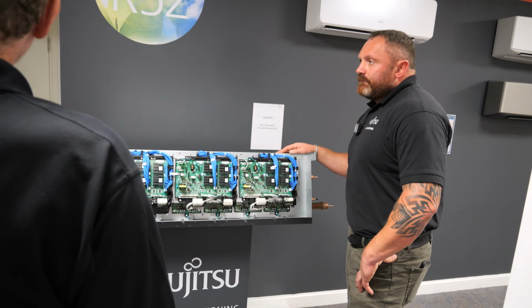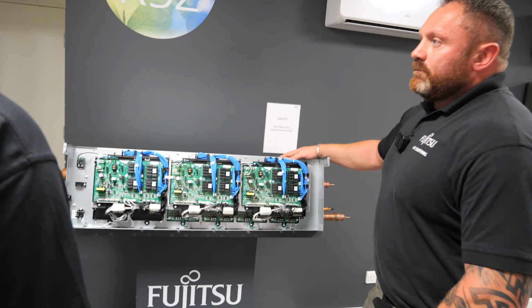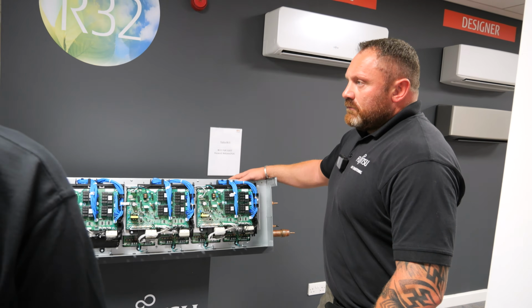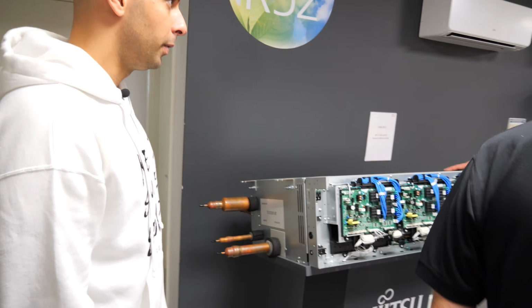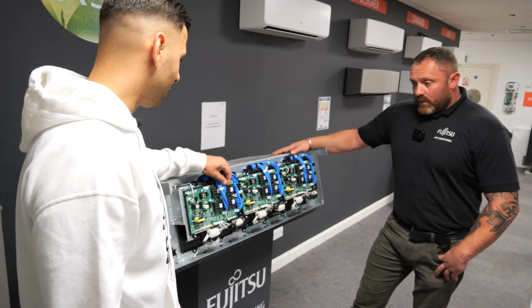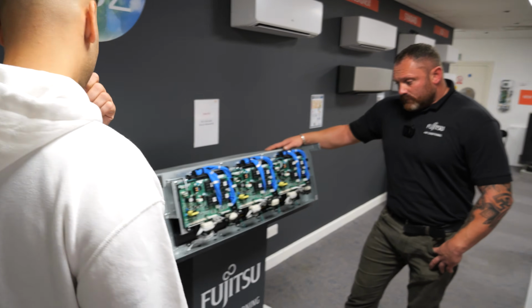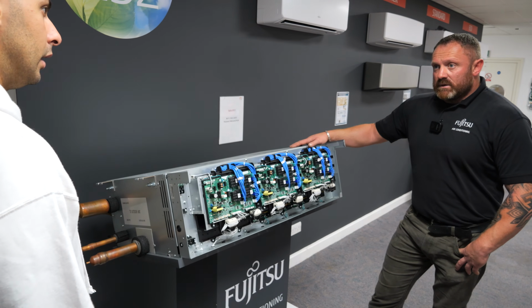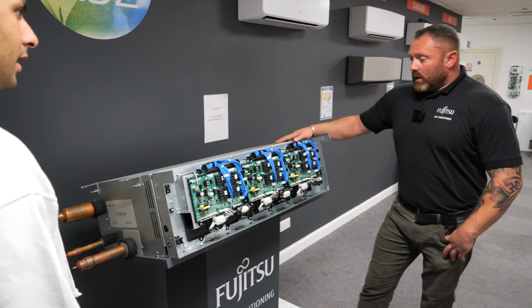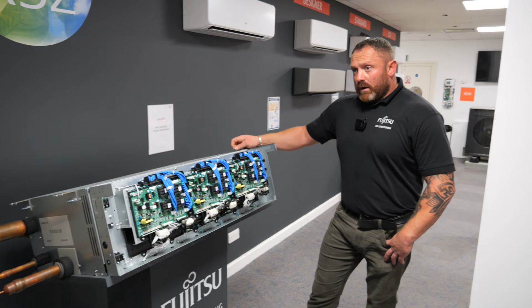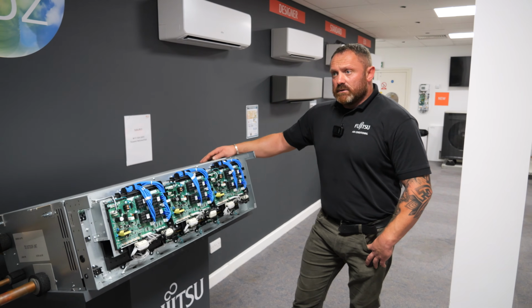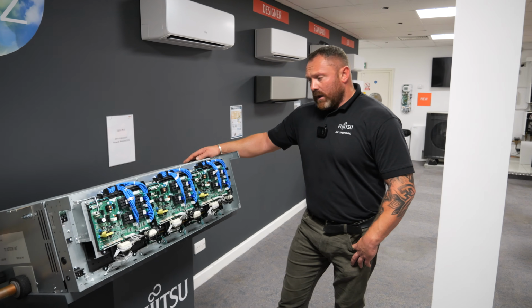In the evaporator, you don't have any expansion valves in here? Weird, so it's quite simple actually. Yeah, very simple, very reliable. It's just a 240 volt solenoid. So you're literally just opening and closing? Yeah, that's it. So no expanding, no balancing? No, it's got a capillary balance line in there to stop noise, for oil, things like that. But yeah, it's just on.